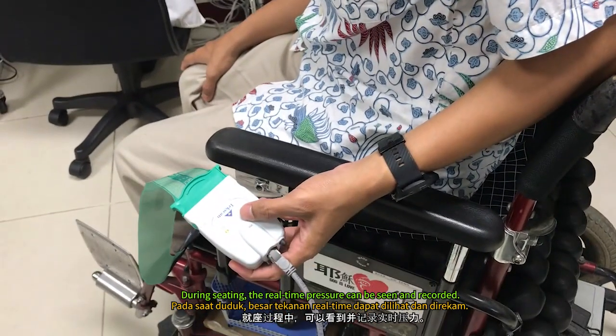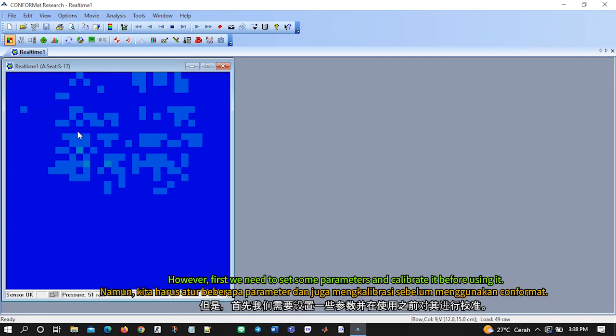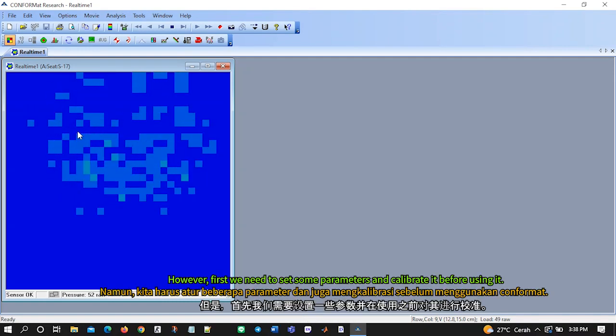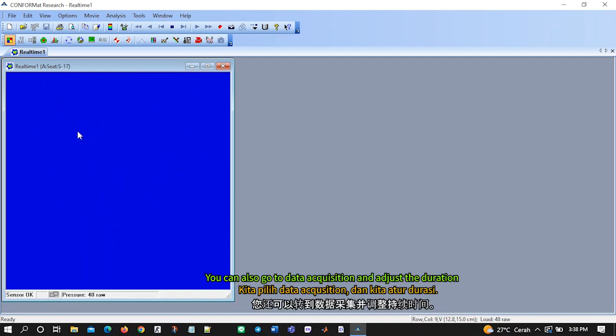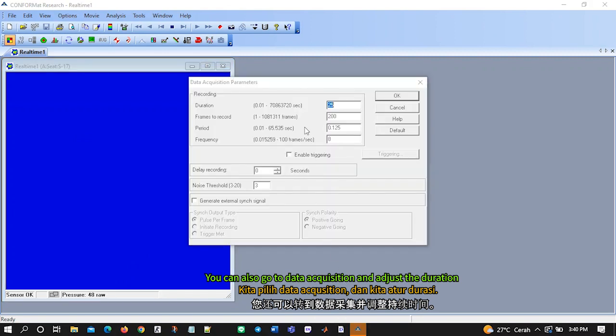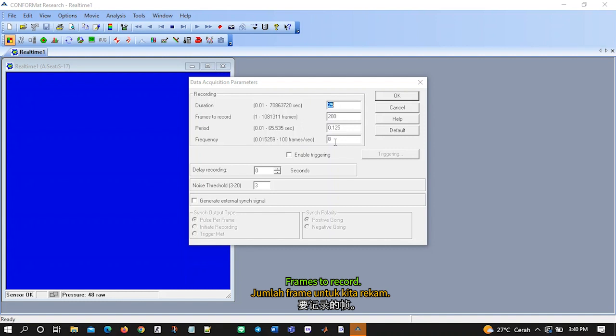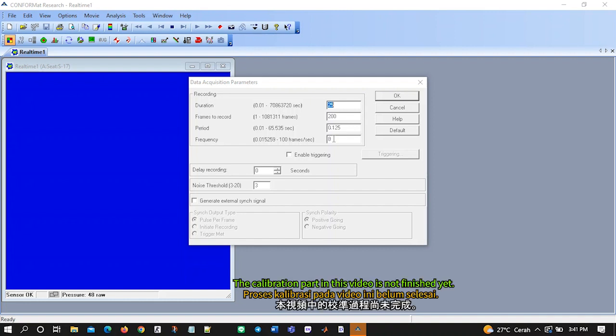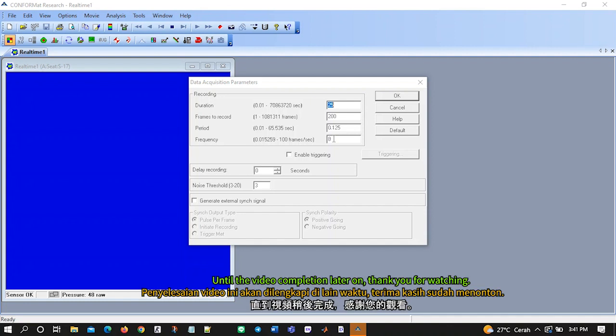During sitting, the real-time pressure can be seen and recorded. However, first we need to set some parameters and calibrate it before using it. You can also go to Data Acquisition and adjust the duration, frames to record, period, and frequency, as well as delay recording and noise threshold. However, the calibration part in this video is not finished yet. Until the completion video later on, thank you for watching.